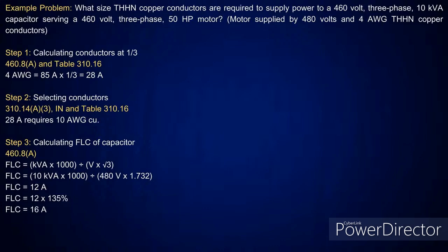So I'm going to take that at a third. And you'll say, where'd I get the third at? Well, you're going to go look at 460.8(A). That's going to tell you to take it at a third. And that's going to give me 28 amps. Okay? Right. Now, we're actually going to end up doing 2 calculations here. The first one is where we're calculating the conductors at a third, and the second portion of this we're going to be where we're calculating the full load current of the capacitor.